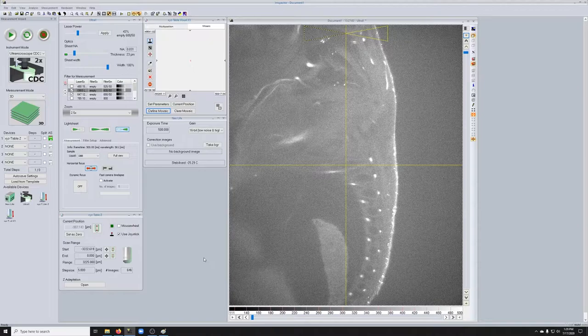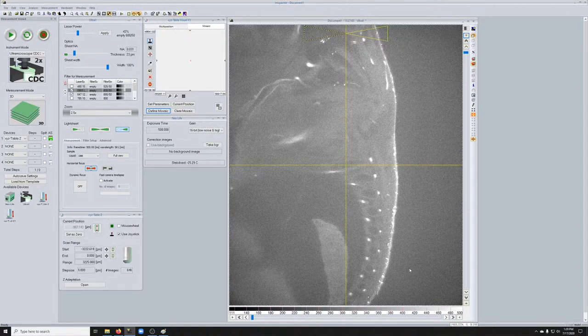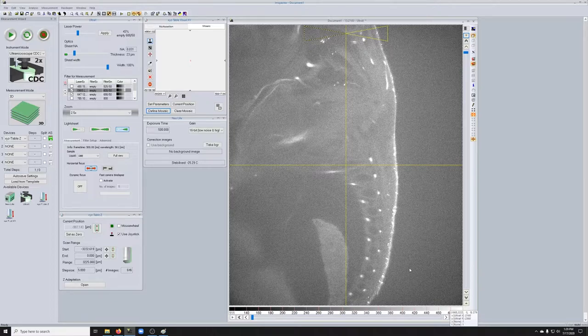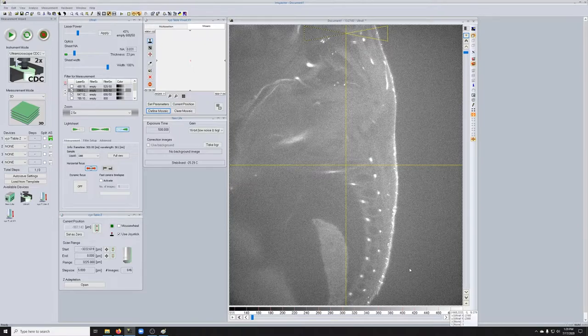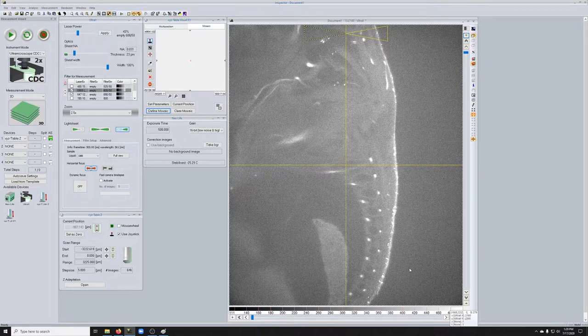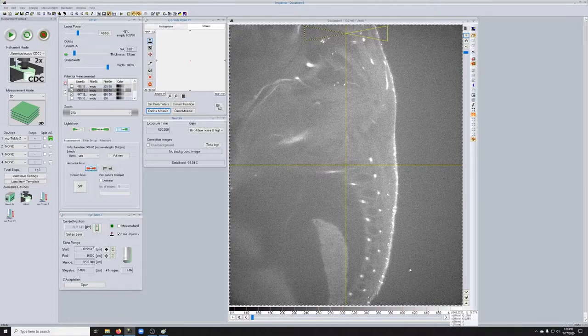the edges of the field of view, particularly the left and right edges, but also the top and bottom and the corners, are of lower quality than the middle. As a result, if you tile over a large area, what happens is that you're trying to then stitch images whose edges are of poor quality. And all of the stitching takes place at those small regions of overlap at the edges. So that actually ends up making the stitching look quite bad.